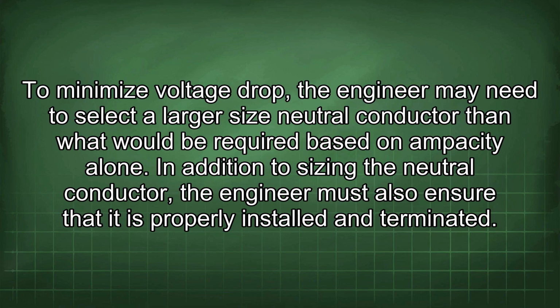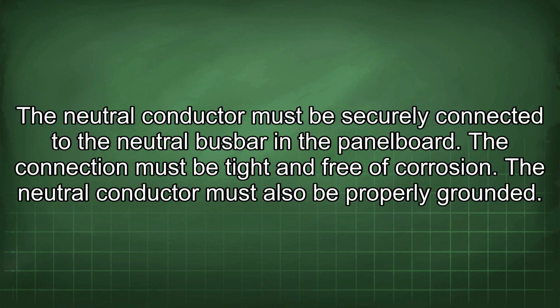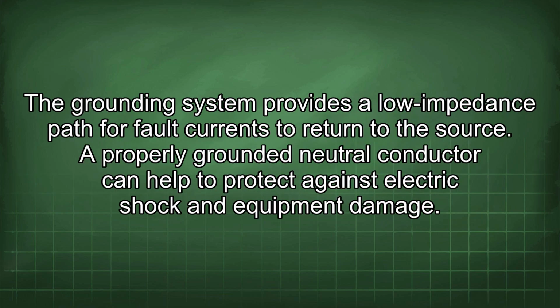In addition to sizing the neutral conductor, the engineer must also ensure that it is properly installed and terminated. The neutral conductor must be securely connected to the neutral busbar in the panel board. The connection must be tight and free of corrosion. The neutral conductor must also be properly grounded. The grounding system provides a low-impedance path for fault currents to return to the source. A properly grounded neutral conductor can help to protect against electric shock and equipment damage.